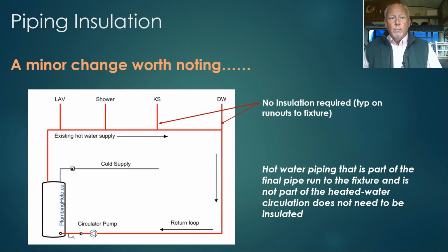One small minor change worth noting is that piping insulation, hot water piping that's part of the final run out to the fixture and is not part of the heated water circulation system, does not need to be insulated. So this was always problematic in the field of where does the insulation requirement start and where does it stop. The previous code required that the insulation run continuous all the way to the stop valve of the fixture.